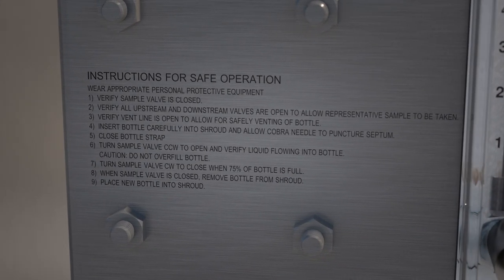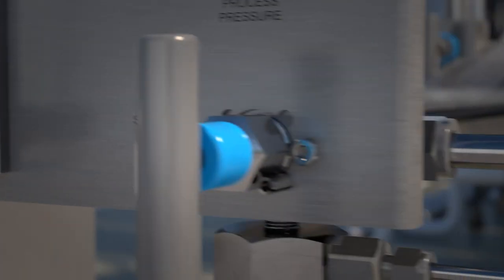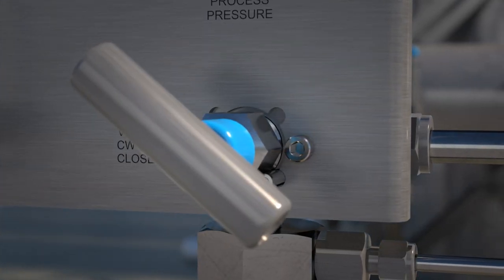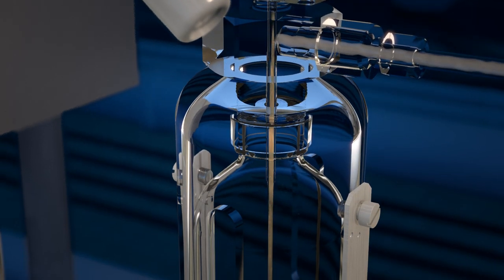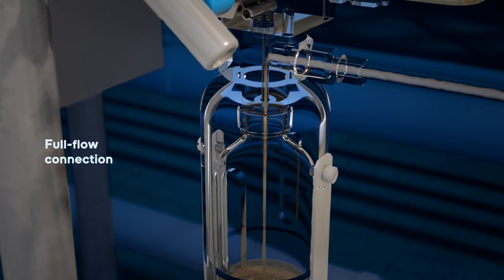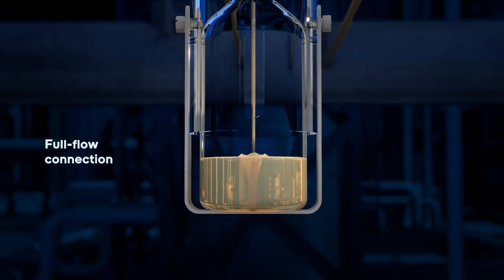The panel includes operating instructions to guide the operator through each step of the sampling process. When the operator opens the sample valve using the multi-turn handle, the process liquid flows through the sample needle assembly to the collection bottle. The valve body is available with one-half to one-inch connections that provide full flow and reduce pressure drops.